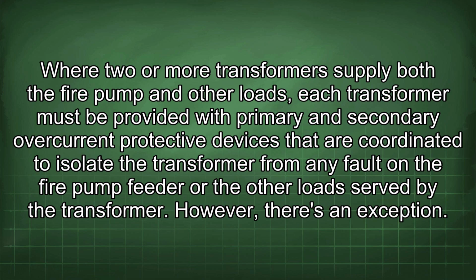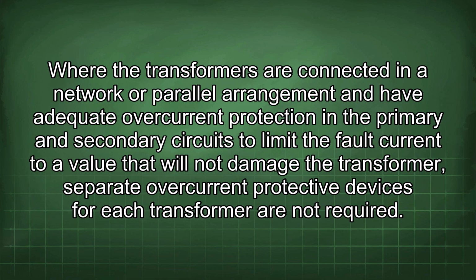However, there is an exception. Where the transformers are connected in a network or parallel arrangement and have adequate overcurrent protection in the primary and secondary circuits to limit the fault current to a value that will not damage the transformer, separate overcurrent protective devices for each transformer are not required.